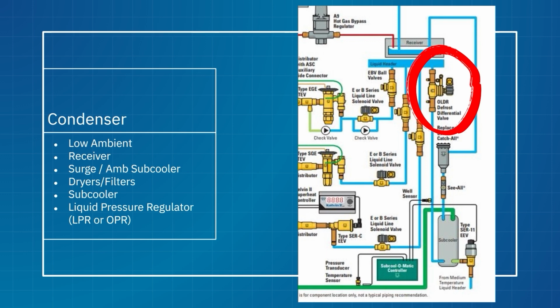This valve is gonna reduce the pressure of the liquid that comes out and goes to my cases. Now the reason it's gonna do that for hot gas is so that I can bring hot gas through my evaporator and it'll flow from high pressure to low pressure. I want to tie into that header. That's why I'm gonna do that.